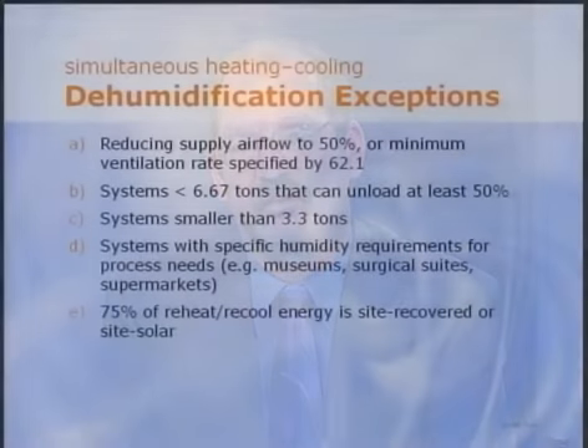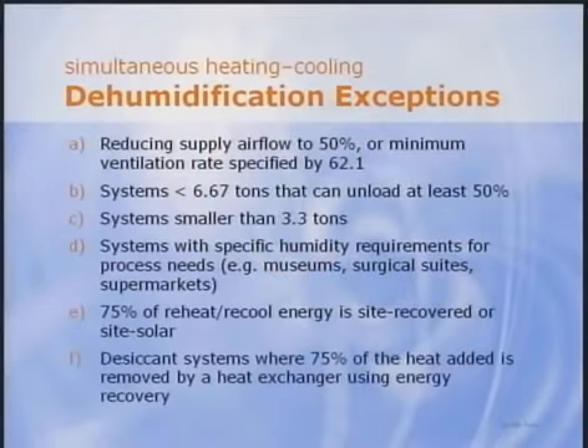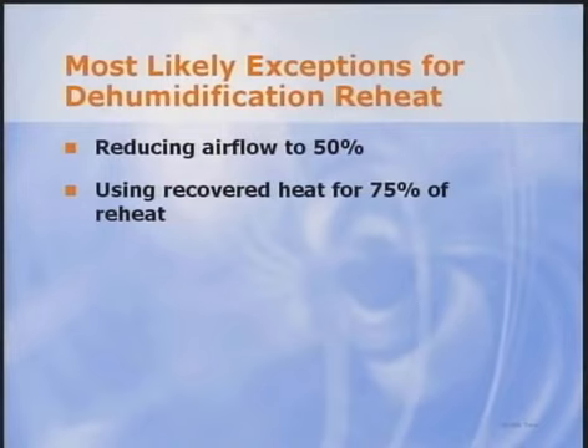There's a broadcast and an engineer's newsletter on waterside energy recovery. The final exception is targeted toward active desiccant systems that dry but also heat the airstream. Often these systems require recooling of that hot, dry airstream. As long as 75% of the heat added by the desiccant is removed by a heat exchanger using energy recovery, the system is allowed. As Dennis showed, most VAV systems don't need humidistatic controls.